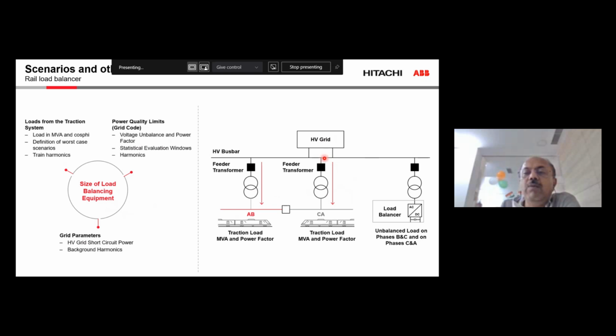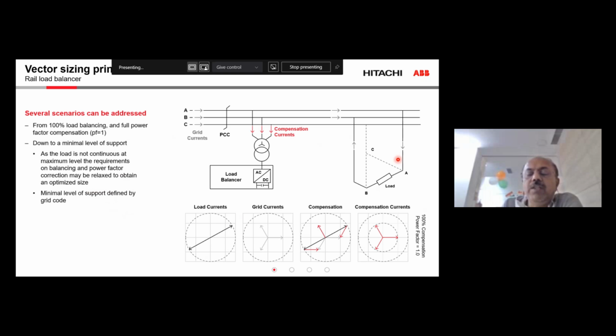Because these alternatively two phases are connected to the individual station, that is where this scenario happens that one side you will have a totally extreme end of the unbalancing, and when they are all working it can be as minimum as possible. So this load balancer understands the scenario in the event of any change in this, and then adjusts its feeding and balances the entire network for both real power and also the reactive power compensation. So that is what is demonstrated here. I will not get into the more technical details.